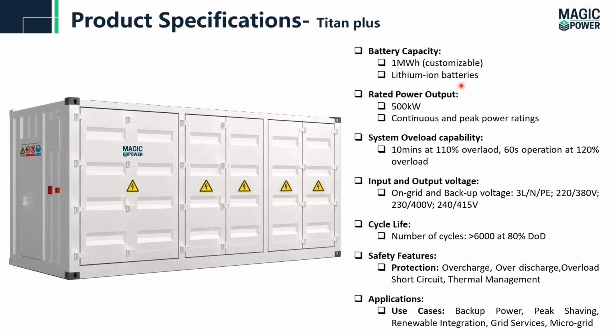The cell technology is lithium ion batteries. The rated output power for the system is 500, or it can be customized according to the requirement, with continuous and peak power ratings. For the system overloading capability, if it is overloaded by 110%, it will run for a maximum of 10 minutes, and in case of 120% overloading, the operation time is reduced to 60 seconds. The input and output voltages, the system is again three phase, so it could be 380, 400, and 415. The life cycle of the batteries is more than 6,000 cycles at 80% depth of discharge.